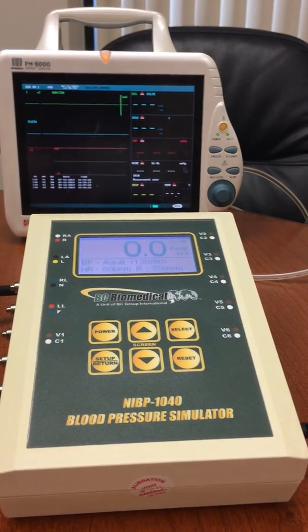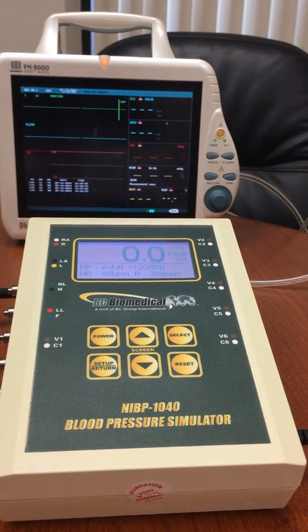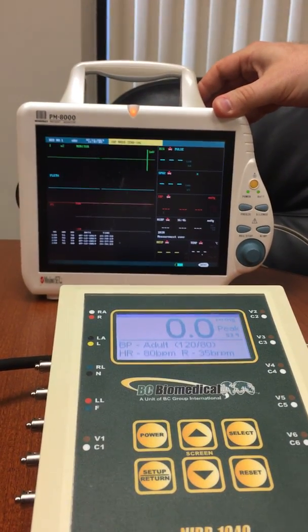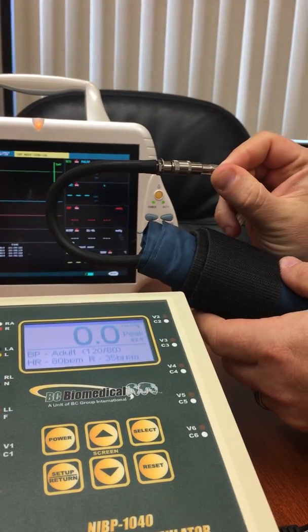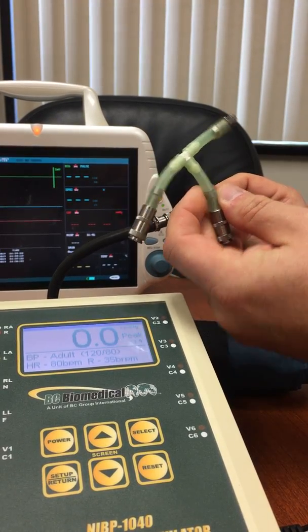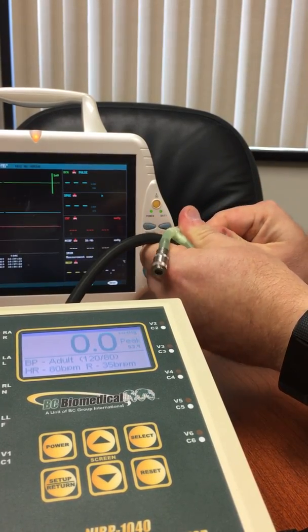In this video we're going to be talking about the NIBP-1040 and how to perform a NIBP simulation. In the background we've got our Mindray PM-8000, and this monitor comes with the standard blood pressure cuff and the quick connect fitting. With our NIBP we received this T, and what we're going to do is disconnect the blood pressure cuff and put this T in series with it.